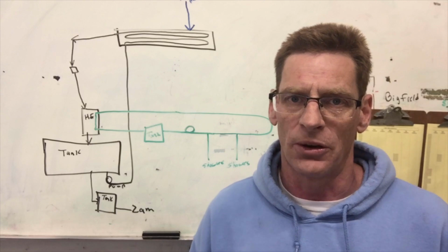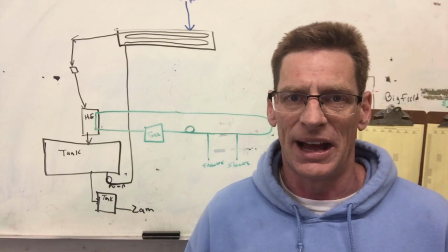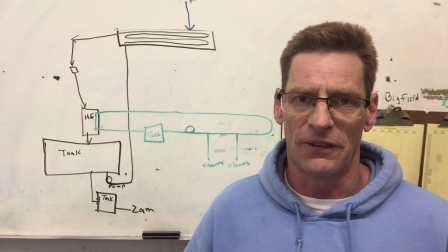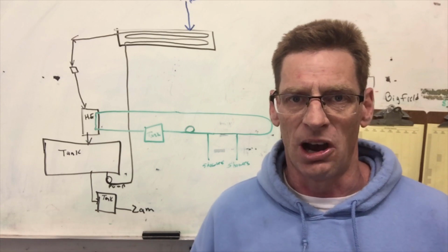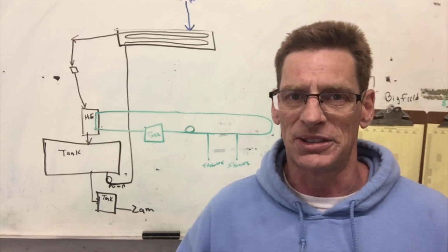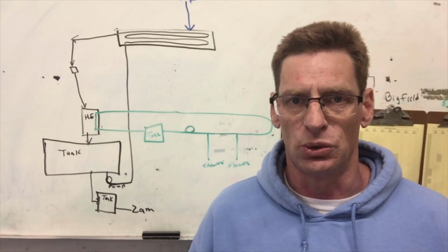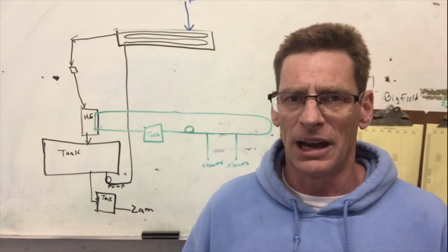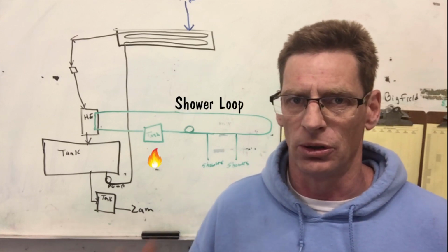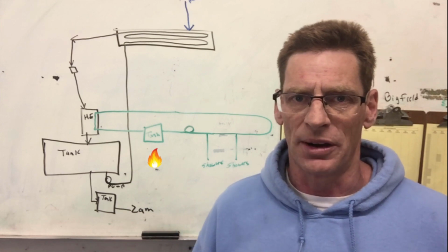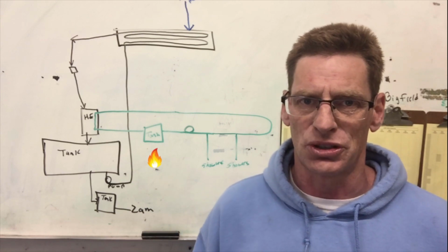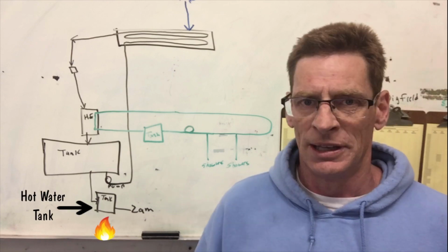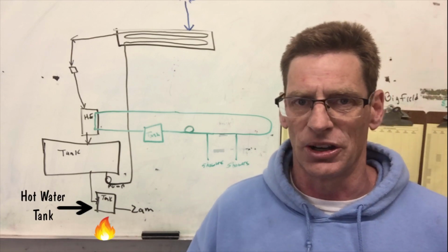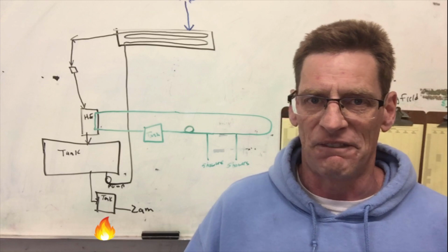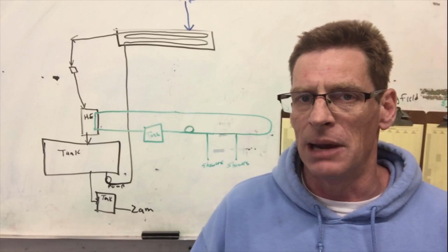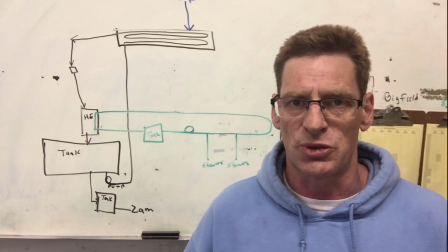Right now we don't have hot water for the showers, but we do have hot water for the Zamboni, so don't worry. We have hot water heaters, but we mainly rely on heat exchangers from the refrigeration system. The water entering our hot water heaters, we only have two, is already preheated. The shower loop uses a residential hot water heater, probably 50 gallons. The one that feeds the Zamboni is a 100 gallon hot water tank.